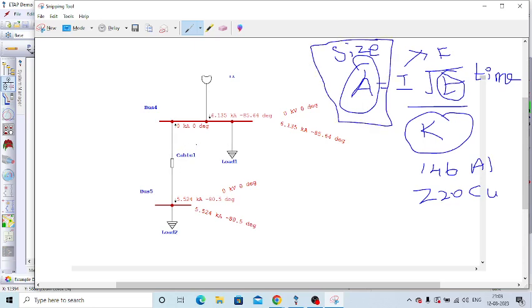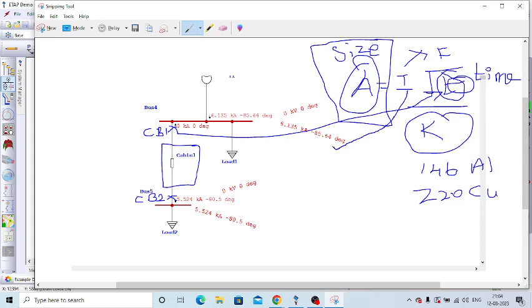Okay, so the cable that we are going to use in this location, we have to select based on this formula. So in this particular cable type of feeder, one circuit breaker will be there. In this location also one circuit breaker will be there. This will be circuit breaker 1, and this will be circuit breaker 2. So this time t belongs to this CB1. In what time this CB1 will operate, that time we have to consider.